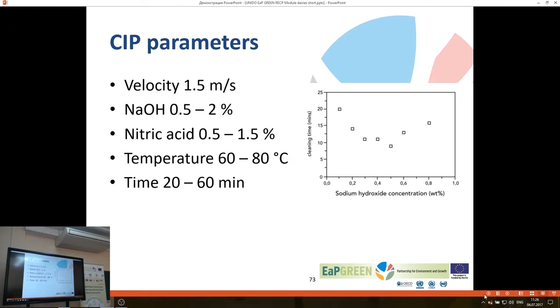Nitric acid, now for neutralization, 0.5 to 1.5%, comparable logic, temperature 60 to 80 degrees, depends on many factors. Mostly it is determined empirically where the actual optimum temperature is, and time 20 minutes if everything is perfect, up to 60 minutes if the equipment is more complicated, the pipes are longer, and so on. But to start optimization, this can be a guideline for parameters of a CIP plant.